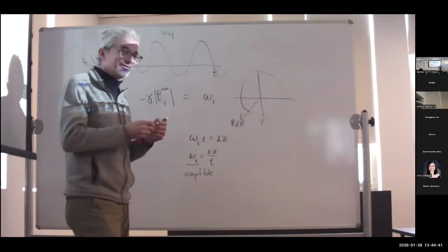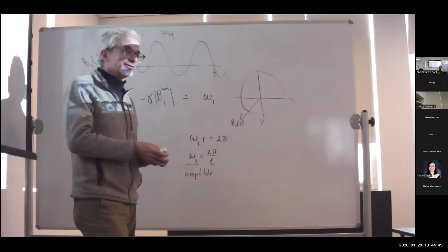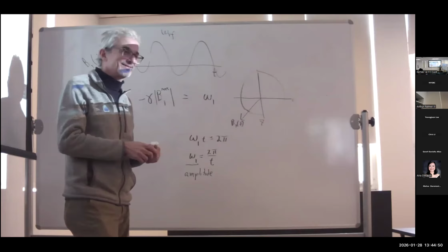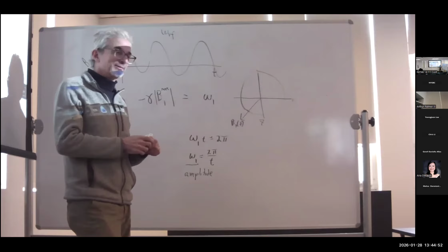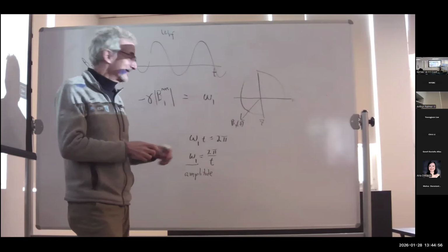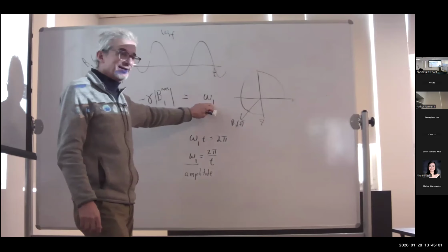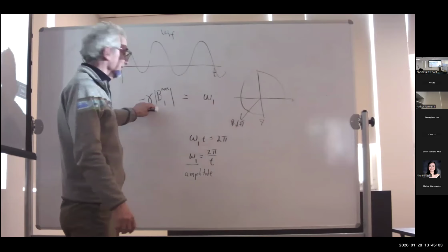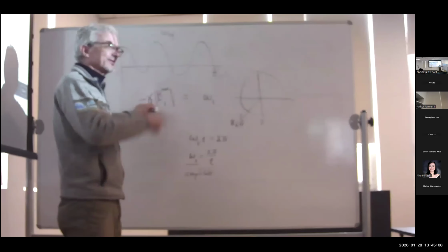And that's why if you go down and look at the spectrometers, the hydrogen amp is only putting out a few tens of watts, whereas the nitrogen amplifier is putting out a few hundred watts. That's to get roughly comparable values of omega 1, even though gamma differs by a factor of 10. So to get comparable amplitudes measured in omega 1, we need 10 times the power, basically, for nitrogen.